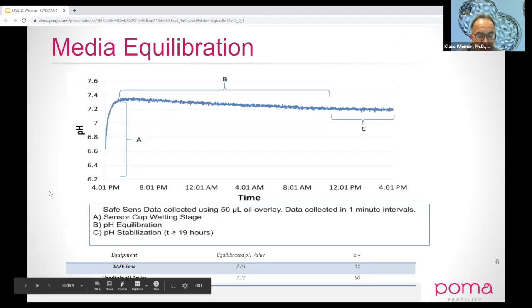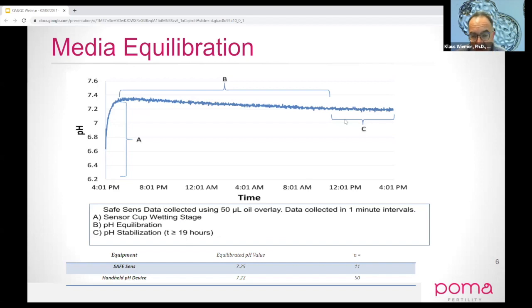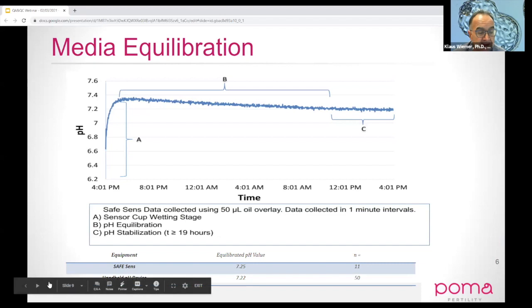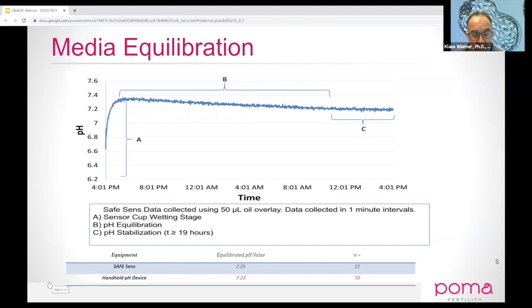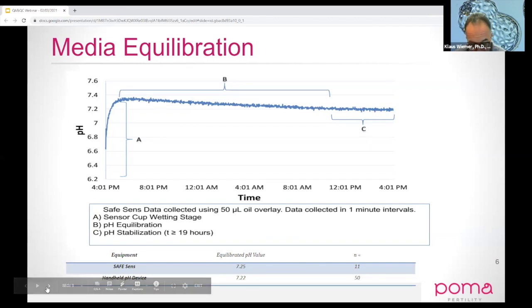This shows how long oil can take to equilibrate. In a MINC incubator with a SAFE Sens continuous application, it actually took almost 19 hours for our culture media to reach pH equilibration. Basically, this has told us that if we start setting up dishes at the end of the day like we used to, they're really not useful until the next day. As a result, we've now started making culture dishes first thing in the morning and giving them at least 19 hours to equilibrate.